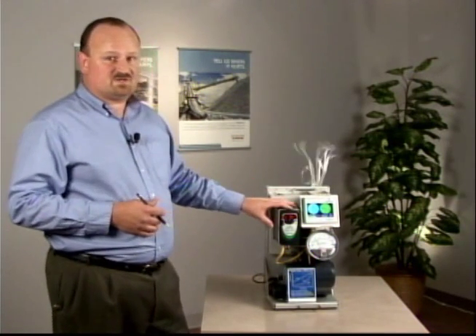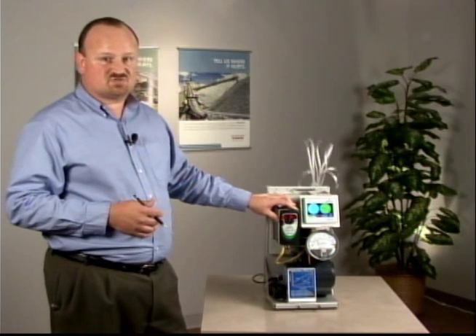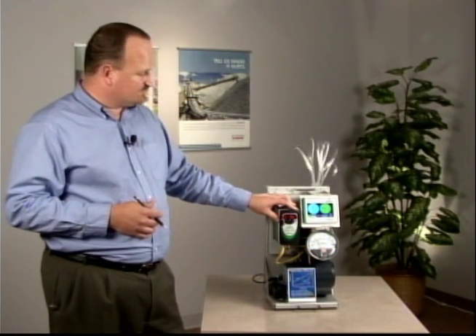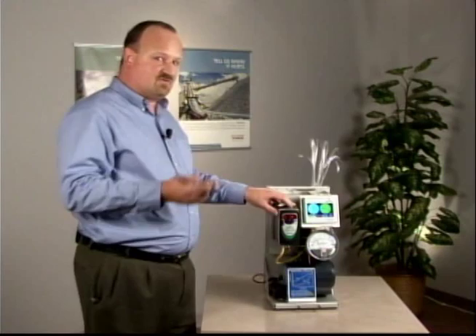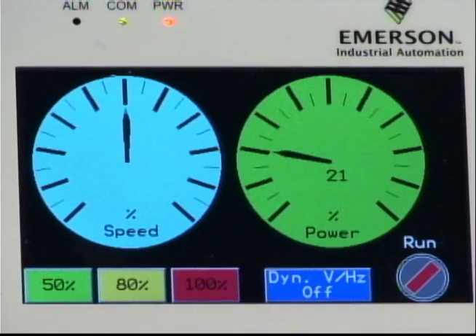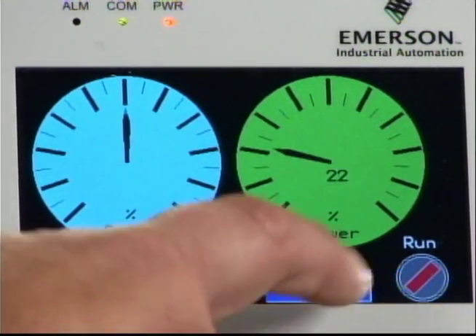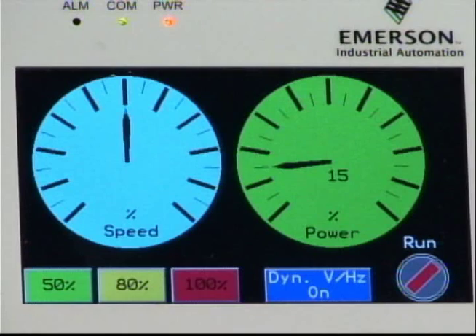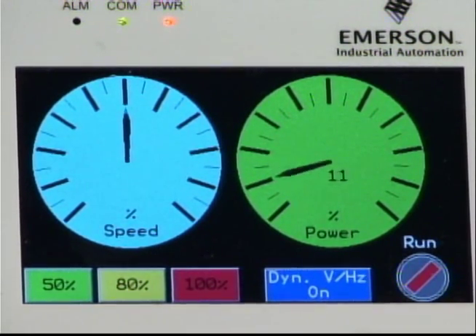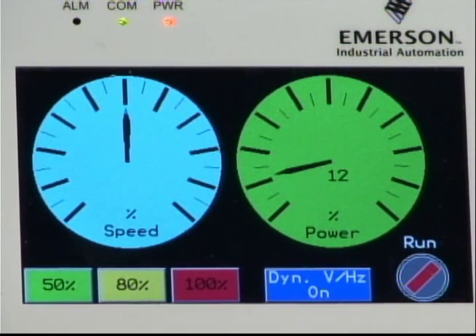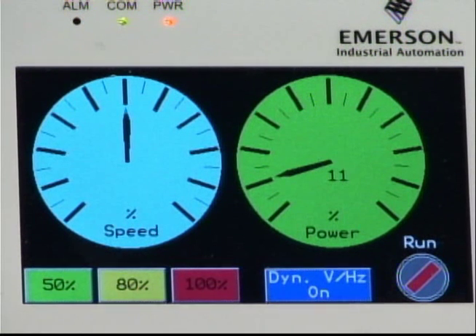This particular variable speed drive is from Emerson Control Techniques, and it includes an optimization feature that can further tune the system to reduce energy consumption. If I turn that feature on, we see the energy consumption has dropped from about 22% to about 11% or 12% — so another 10 points in reduction.